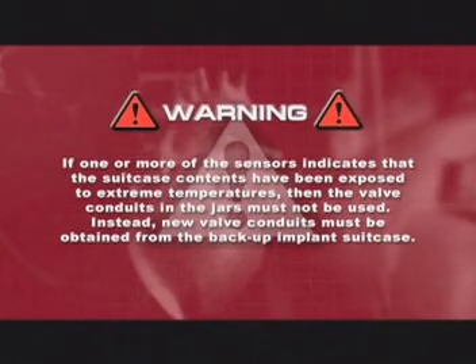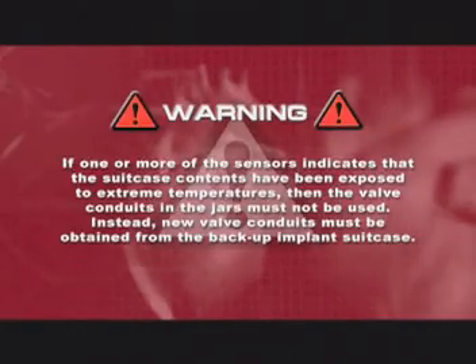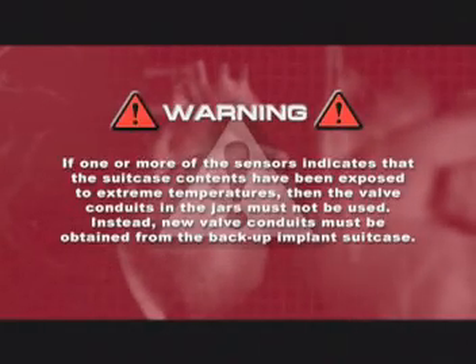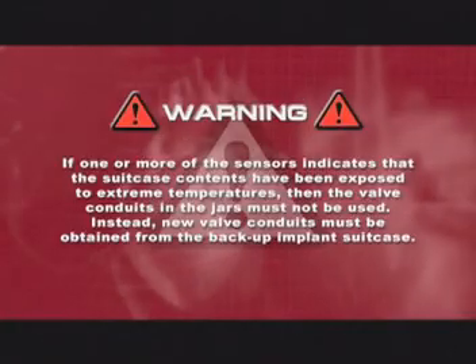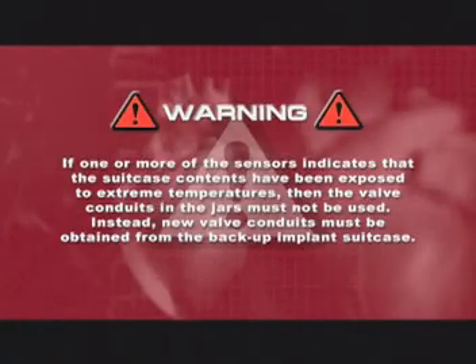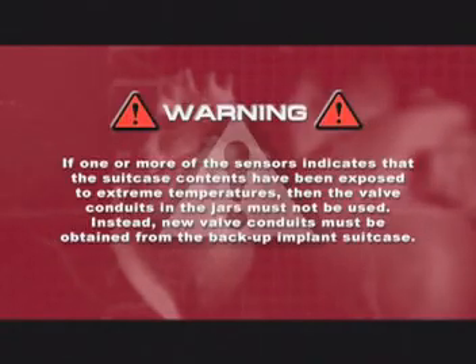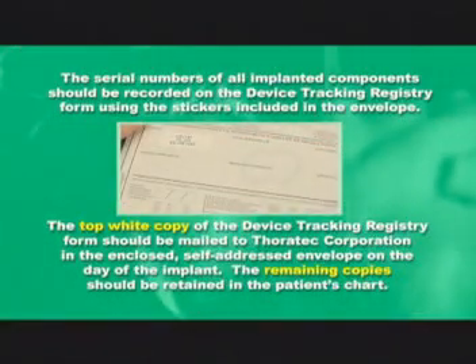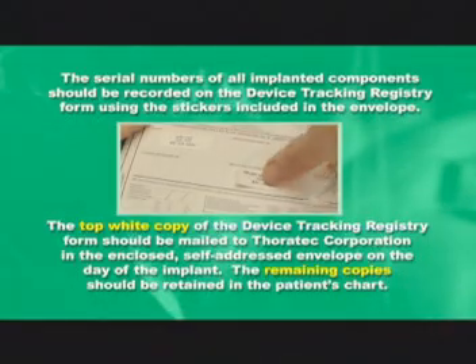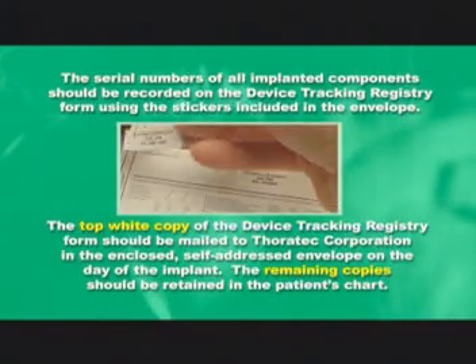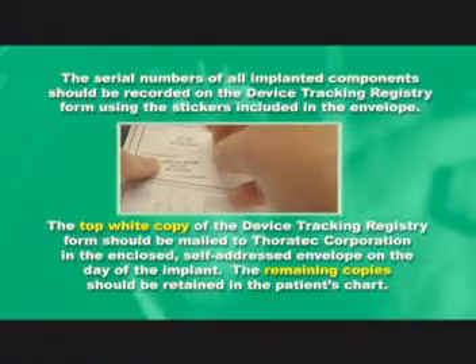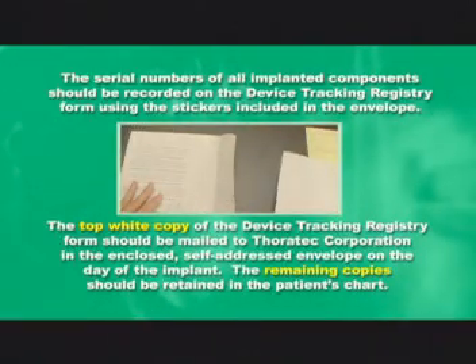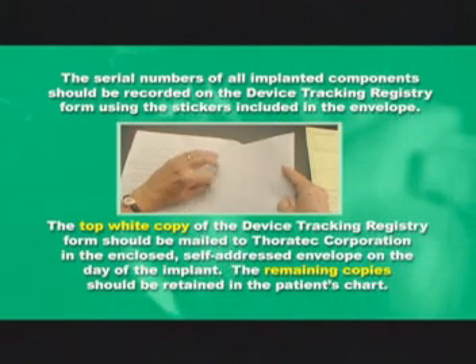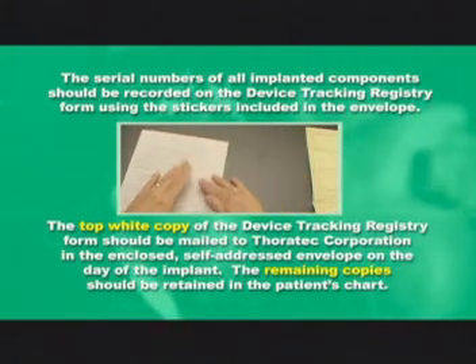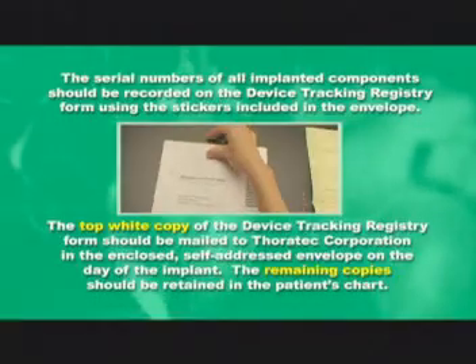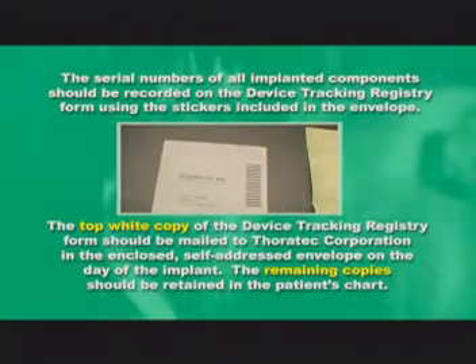Warning: if one or more of the sensors indicates that the suitcase contents have been exposed to extreme temperatures, then the valve conduits in the jars must not be used. Instead, new valve conduits must be obtained from the backup implant suitcase. Note: the serial numbers of all implanted components should be recorded on the device tracking registry form, using the stickers included in the envelope. The top white copy of the device tracking registry form should be mailed to Thoratec Corporation in the enclosed self-addressed envelope on the day of the implant. The remaining copies should be retained in the patient's chart.